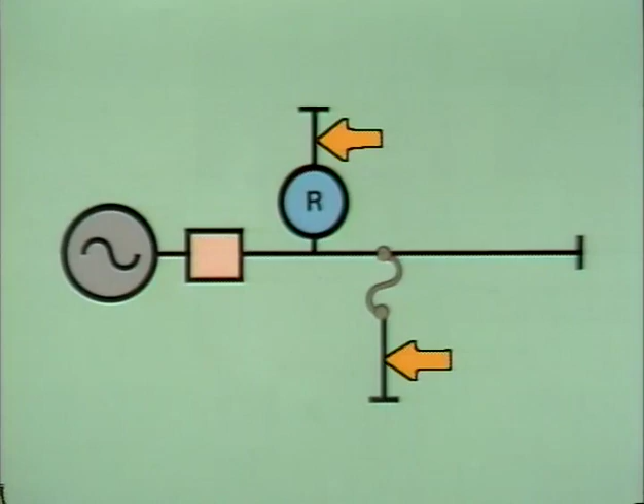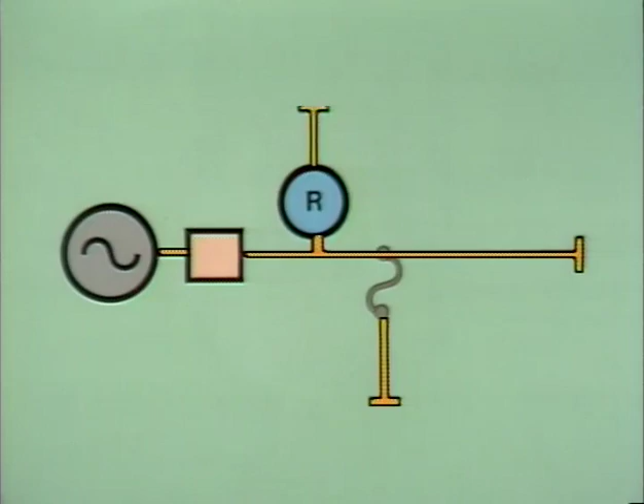During normal operation, current flows from the power source through the circuit breaker and through the main feeder line. Current also flows from the feeder line through the recloser to this branch line. And it flows through the fuse to this branch. So current normally flows through the main feeder line to the lines branching off it. Now, like most electrical hazards, faults can occur almost anywhere in an electrical system. Suppose a fault develops here.